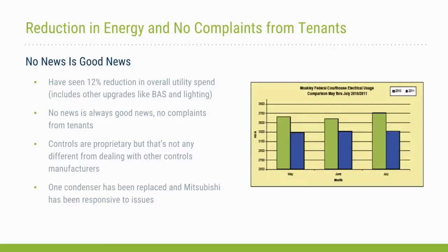Well, like many of you in the field, no news is good news, and we do not hear a lot about the VRF system at the Moakley, which is for us a great success. When we look at the system, we see that we've had a 12% reduction in overall utility spend. To be upfront about that, that does include other upgrades such as BAS and lighting, and since this did not have the type of, as spoken about earlier, we didn't do full M&V on this as it was an ARRA upgrade and not so much a straight up GPG project like some of the other ones. A portion of that is for the VRF system.